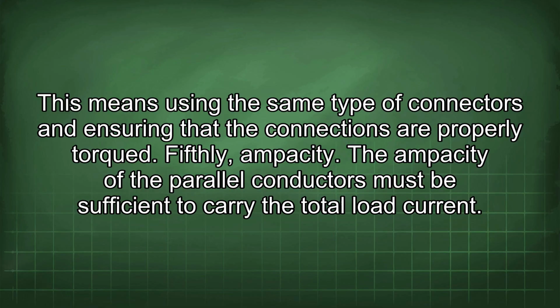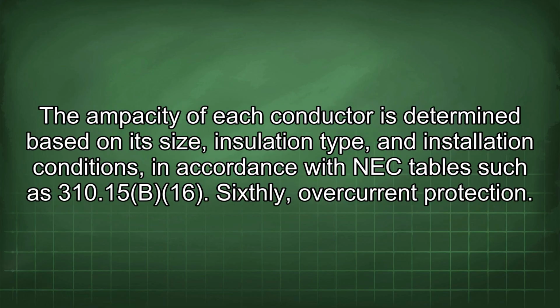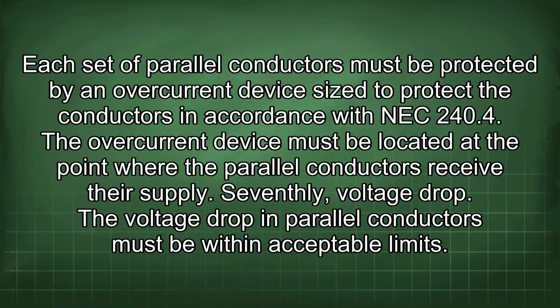Fifthly, ampacity. The ampacity of the parallel conductors must be sufficient to carry the total load current. The ampacity of each conductor is determined based on its size, insulation type, and installation conditions, in accordance with NEC tables such as 310.15(B)(16). Sixthly, overcurrent protection. Each set of parallel conductors must be protected by an overcurrent device sized to protect the conductors in accordance with NEC 240.4.